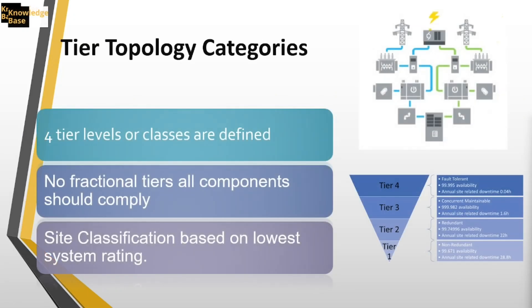Moving on to tier levels: in a data center, there are four tier levels from tier one to tier four — or class one to class four depending on whether you follow Uptime, ITU, or different standards. There are no fractional tiers. If your power is designed to tier three but your cooling is tier two, your data center will be tier two. A tier level is always based on the lowest-tier system rating in your data center.